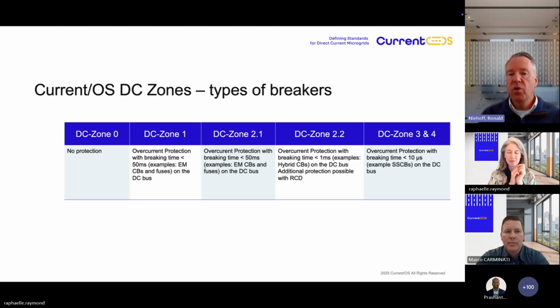So zone 3 and 4 have high speed, 10 microseconds, semiconductor breaker protection where standards are currently developed in IEC. There is an IEC 60947-10 in progress for generic applications, and there is also a 63464-1 breaker family in progress in IEC SC23E, and this is more for residential and similar application.